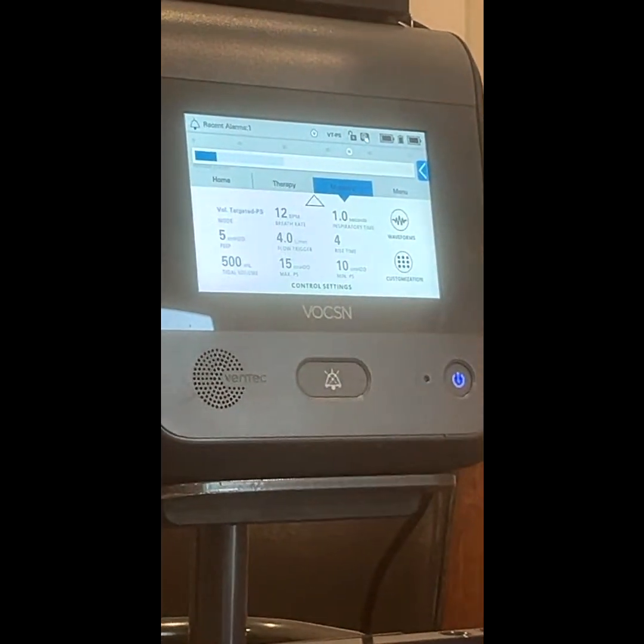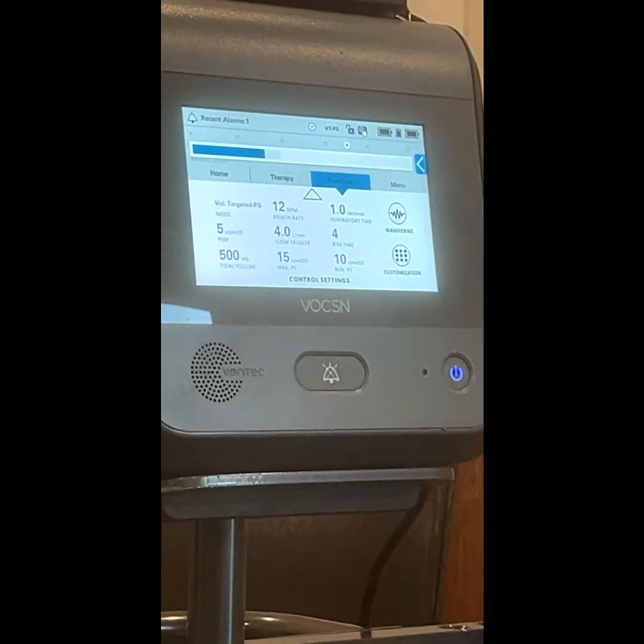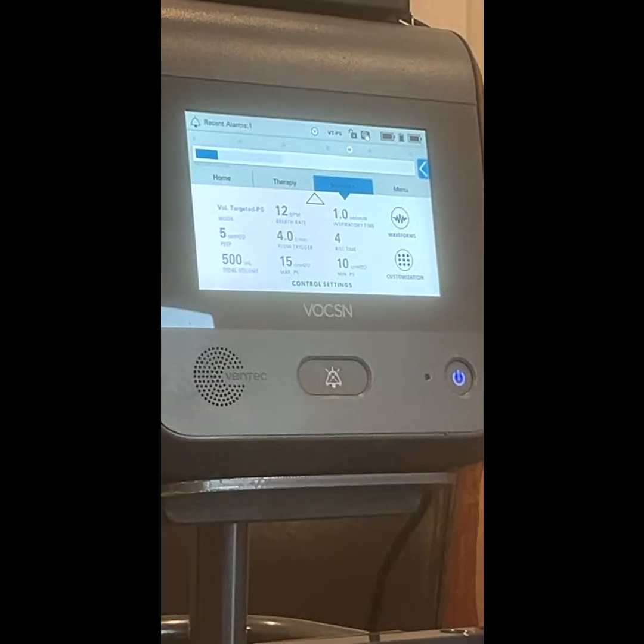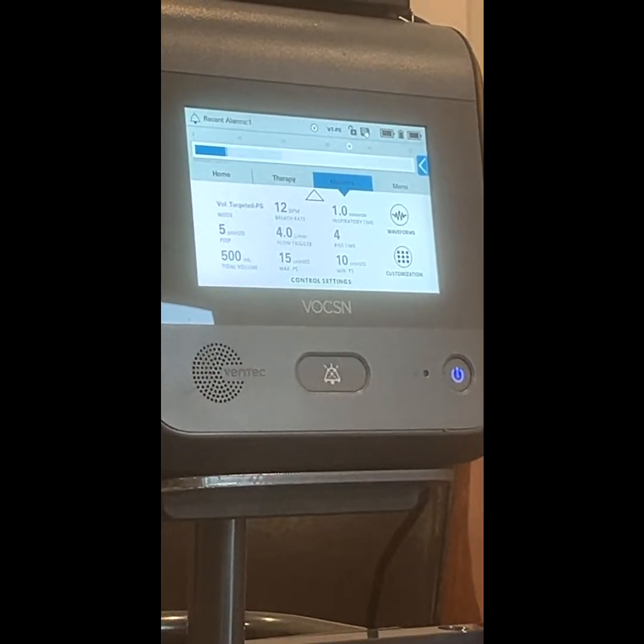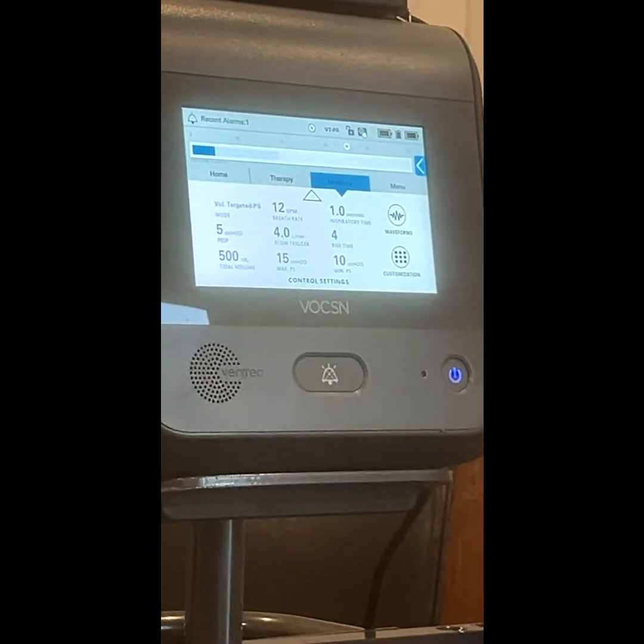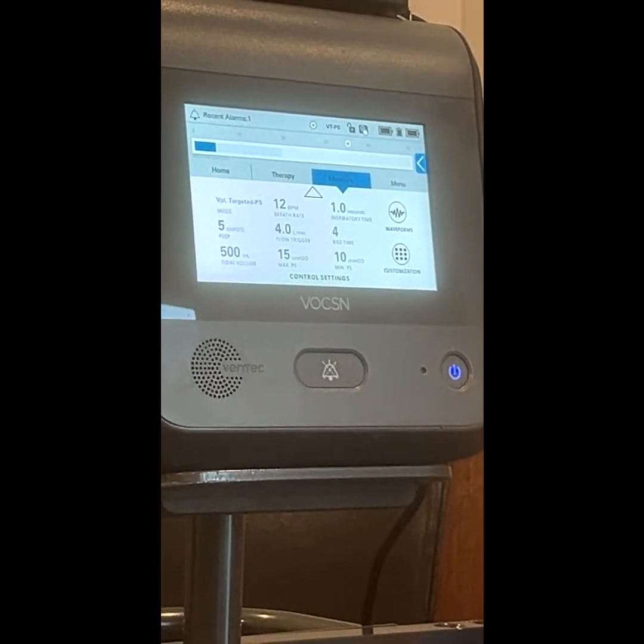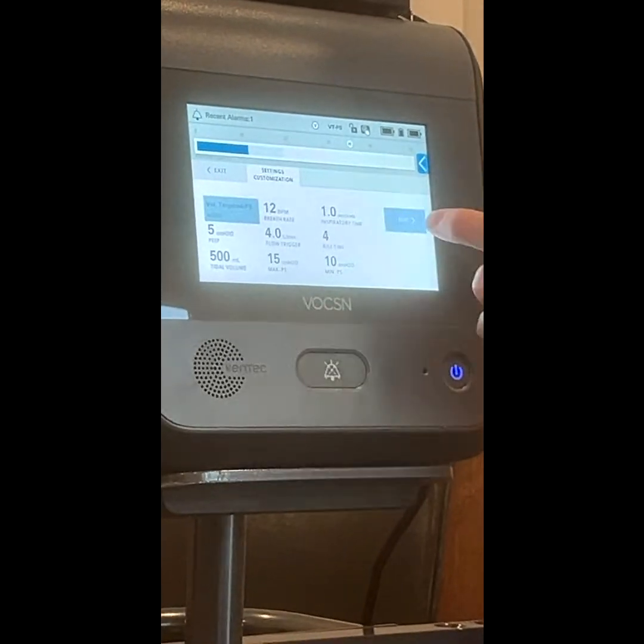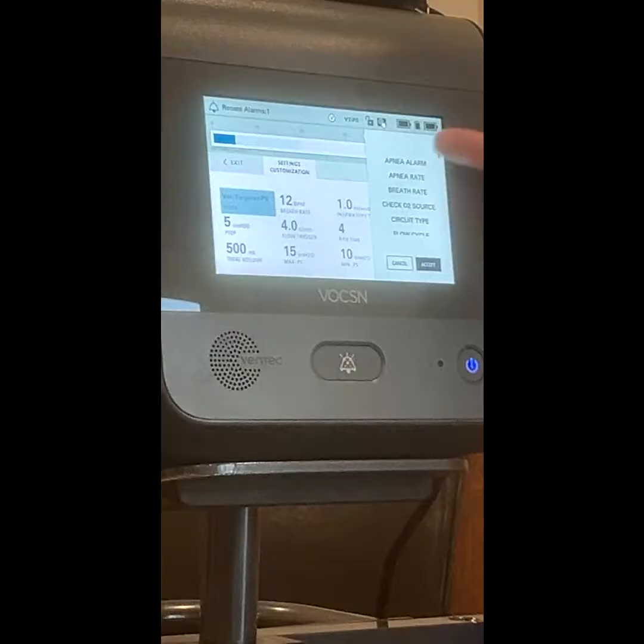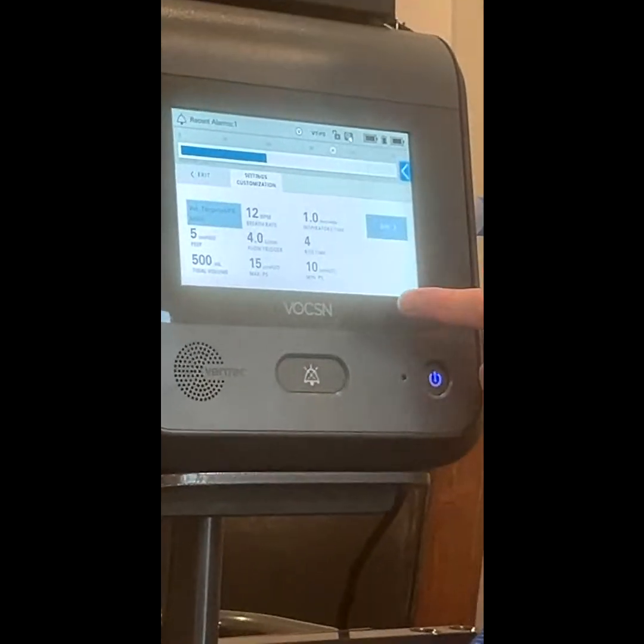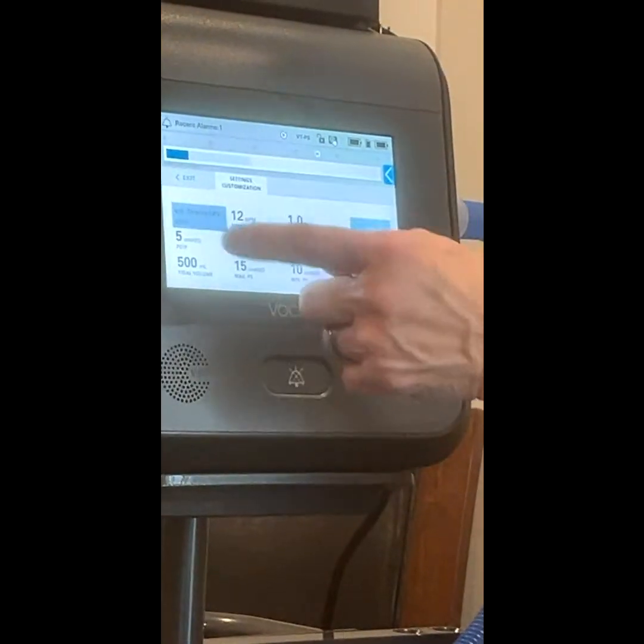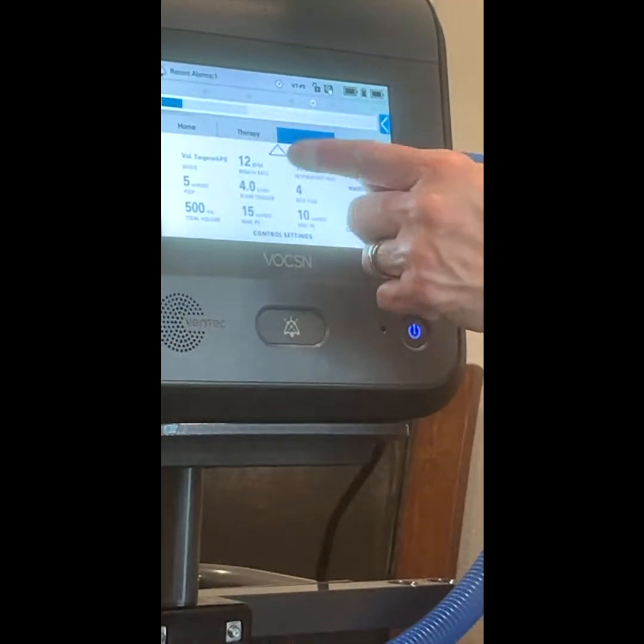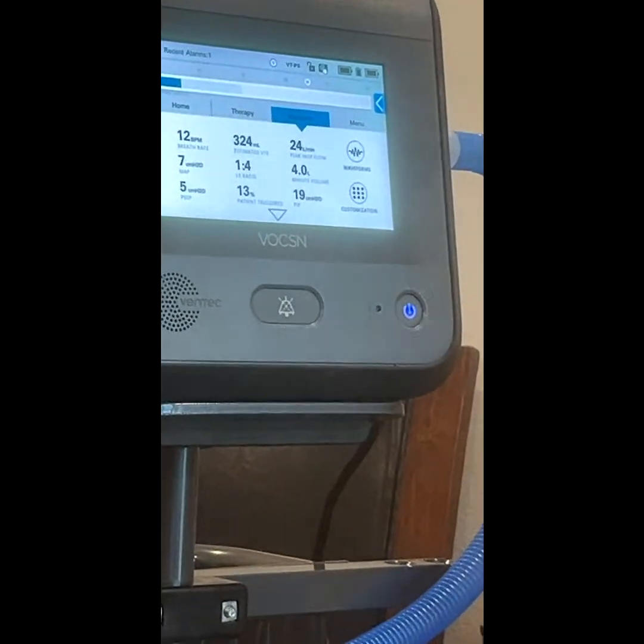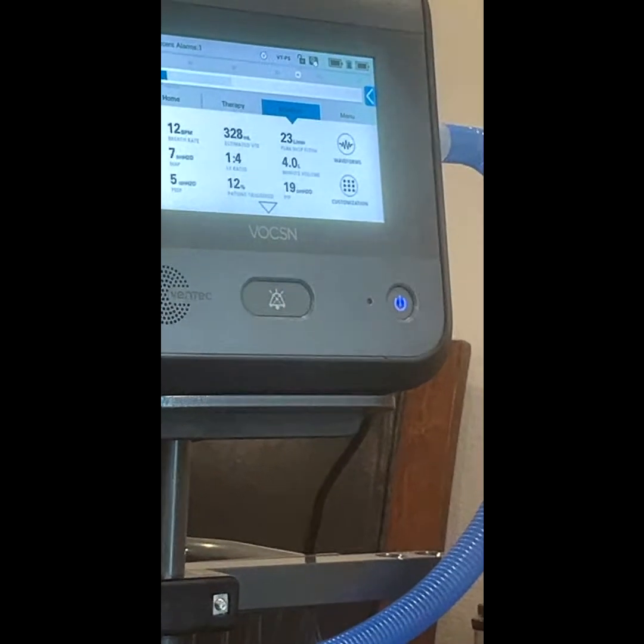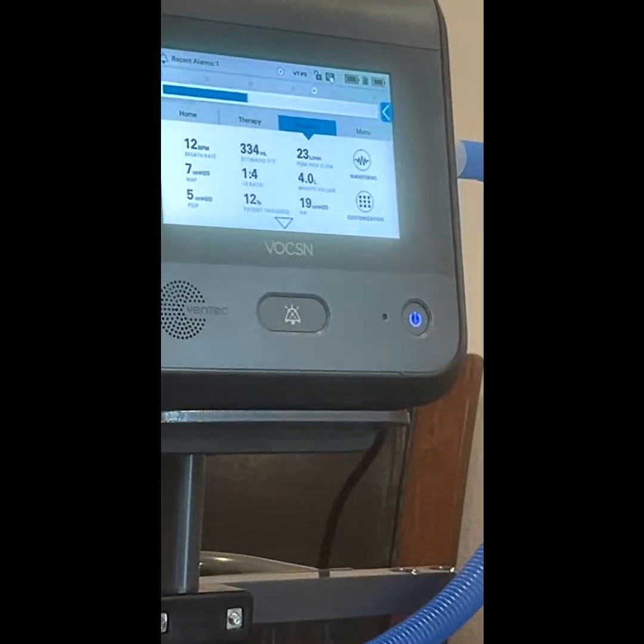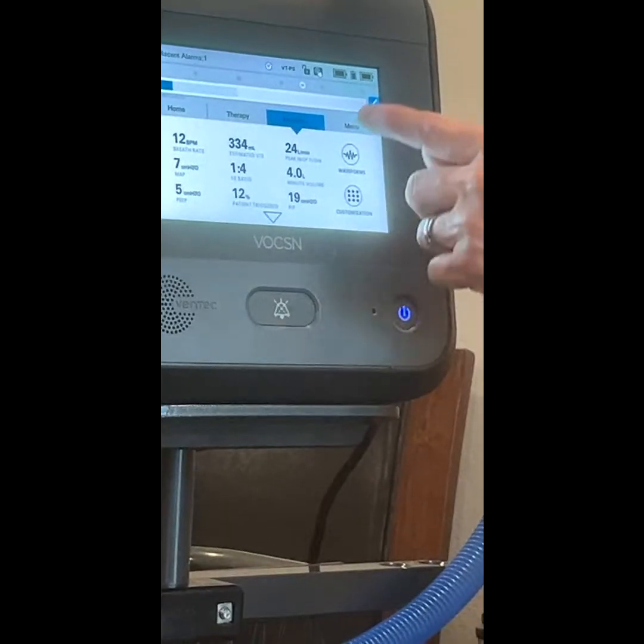So this is their settings. We got volume targeted pressure support, which is the same thing as AVAPS. But they can't put AVAPS because of the patent. So now it's volume targeted pressure support. Mode, that's the mode. If I want to customize that, I hit edit. I can add these here, or I can go ahead and exit out and go somewhere else and look at it. But right here it says VTPS, volume targeted pressure support. And you can go to your monitor.